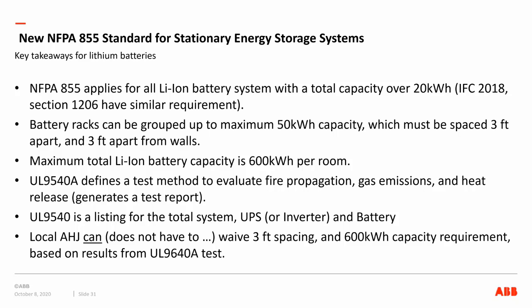And one difference is that it applies to lithium ion batteries if the total energy capacity of the battery is over 20 kilowatt hours. For VLA, lead acid batteries, 855 applies too, but only if the battery is bigger than 70 kilowatt hours. And by the way, if this is a UPS battery, and the UL standard for UPS is 1778, the VLA battery can be listed to 1778 as well, and if it is, then 855 doesn't apply.